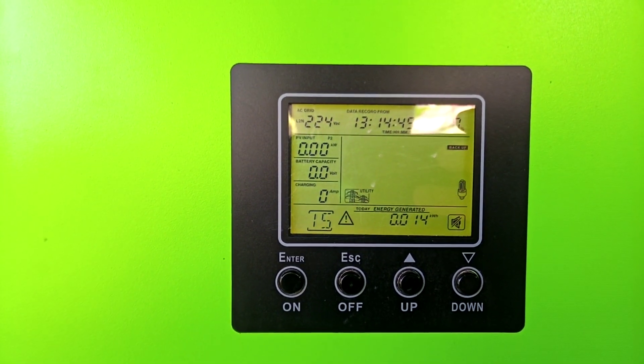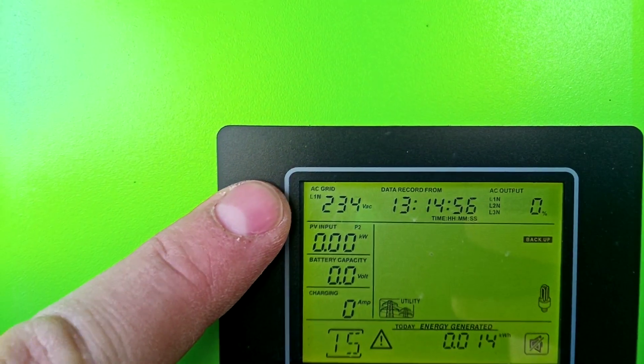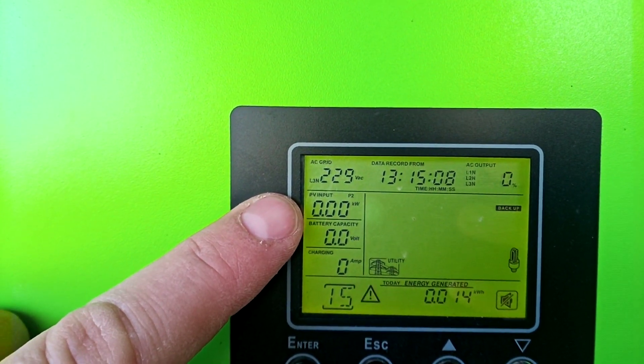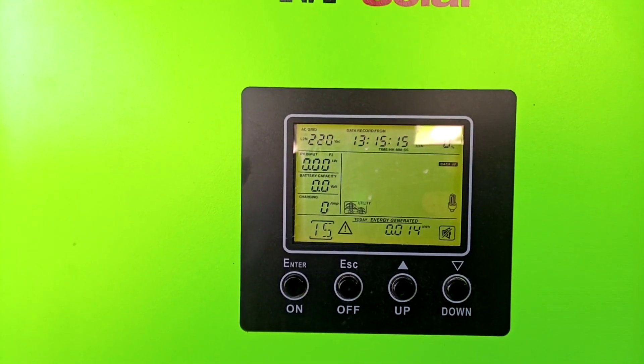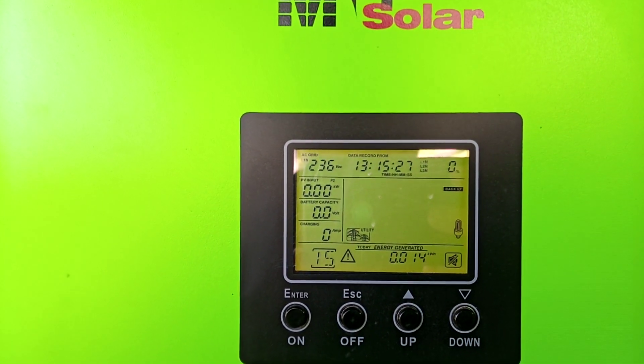Warning 15 — I think it's missing battery. Grid line one is okay, line two and three are all in a good range. The active mode is grid with backup two. Okay, let's start the solar system — two strings, each about 500 volts.